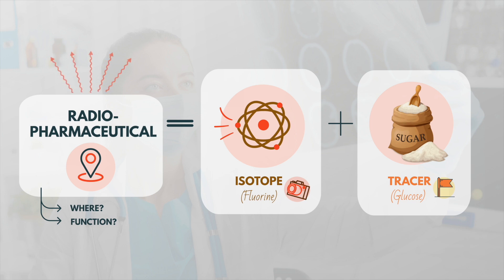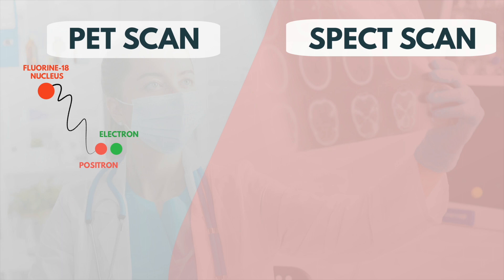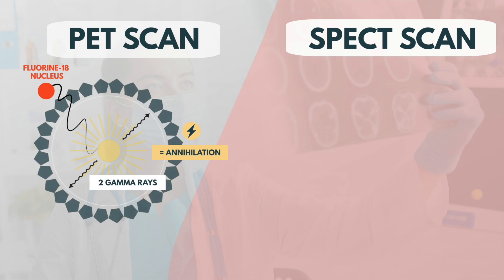Both SPECT and PET radiopharmaceuticals decay by emitting gamma rays, which are picked up by a special camera, but they both do it in a different way. Fluorine-18 produces small particles called positrons. When a positron encounters an electron, which happens very quickly in the body, both particles vanish in a burst of energy. This energy comes in the form of two gamma rays that travel in opposite directions and can be detected by the PET scanner. Only gamma rays that interact at the same time with a pair of detectors are recorded, and the trajectories trace back to the point of annihilation, allowing a computer to form an image.